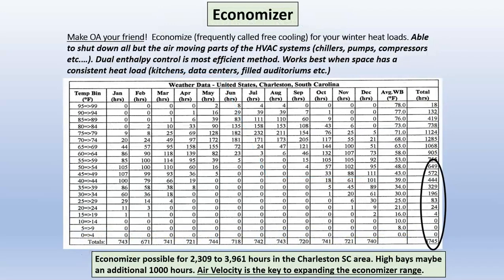Economizer. The economizer is using outdoor air for cooling instead of all the mechanical systems that you may have, such as chillers, pumps, compressors, whatever. It allows you to use outdoor air. Now I use this graph because commonly I hear, like in the area I live around, Charleston, South Carolina, I hear, well, you can't do it here, it's too hot. So you get out your little bin sim here, and it shows you that there's 2,300 to 3,900 hours that you might be able to economize. Most of them are at night, early in the morning, but I mean, there is opportunity there.